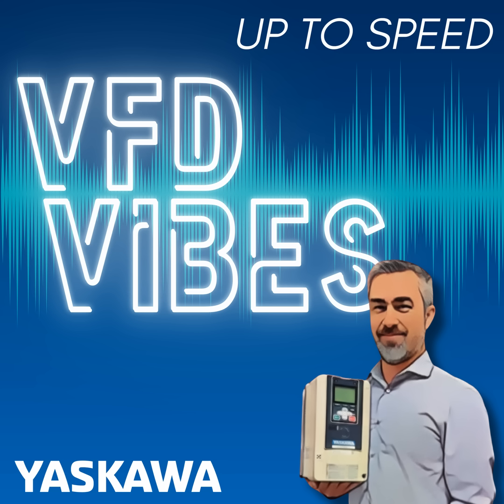So those conditions when we test it, if there's conditions where we tested it, hey, the drive was inside of another enclosure, the drive was outside of an enclosure with the NEMA 1 kit, all those kinds of things, however we tested it and got it to pass is how it must be used. And that's why you see things like minimum enclosure requirements for some of the protective devices. That makes sense, because if it can withstand a current in one condition, but it's a lower amount of current in another, then that all needs to be documented and made sure that those instructions are adhered to.